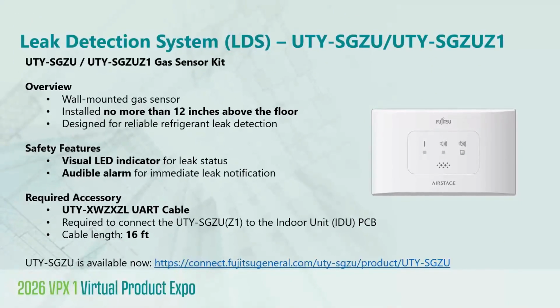Now let's talk about the SGZU and SGZU Z1. Wayne did give you a little introduction about this accessory. I just want to highlight a couple of features and we'll move forward after that. Now, this is a wall-mounted gas sensor and can be installed no more than 12 inches above the ground. And this sensor is designed to detect the R32 refrigerant leak. The sensor includes visual LED indicators to show the user leak status, as well as an audible alarm beep that will alert the occupant if there's any leak.